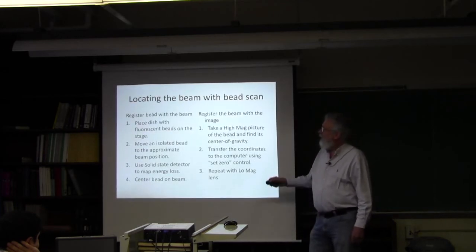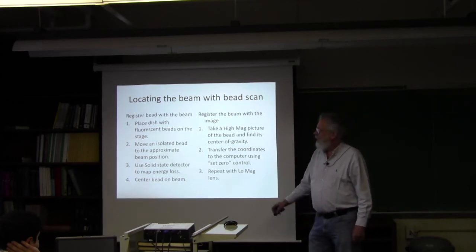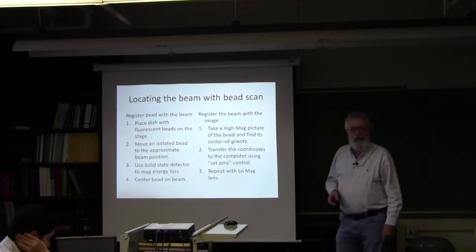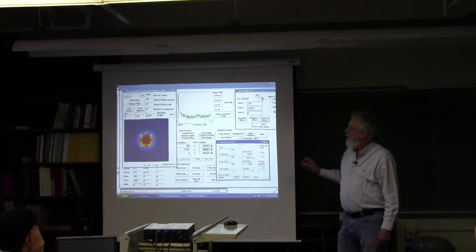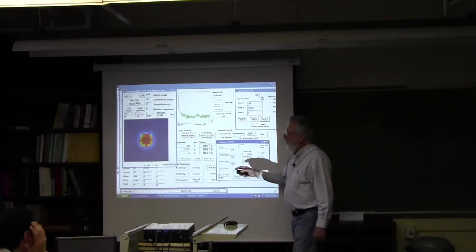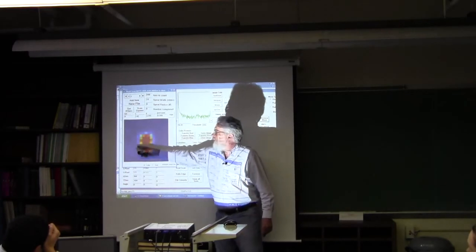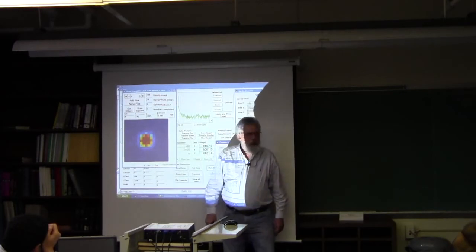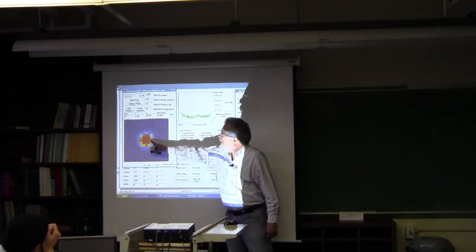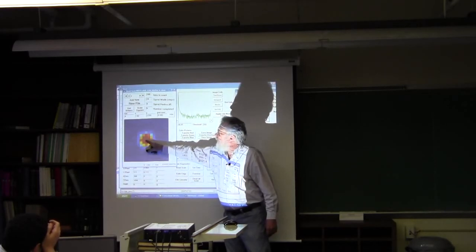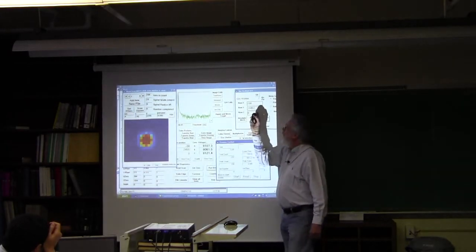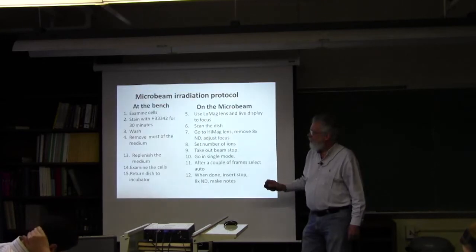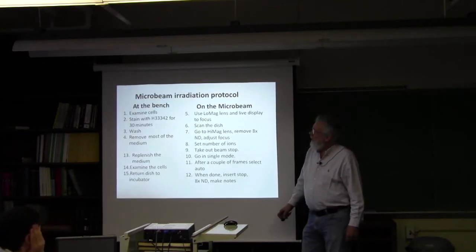These are the steps going through the bead scan. This is in gory detail. I think you have a slightly different version in your books. We'll go through this as an exercise tomorrow. What you get is a picture like this where the dark blue areas are where the particles are missing the bead and the red areas are where the particles are going through the bead. Either the program locates it or you can click on the center of this, and that tells you where you have to move to actually center the bead on the beam axis.